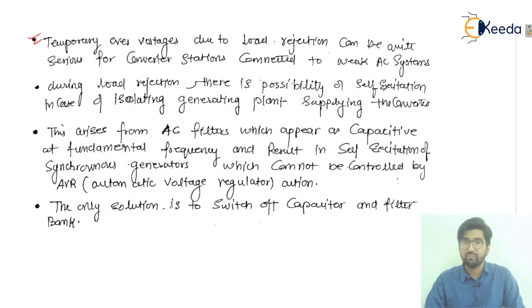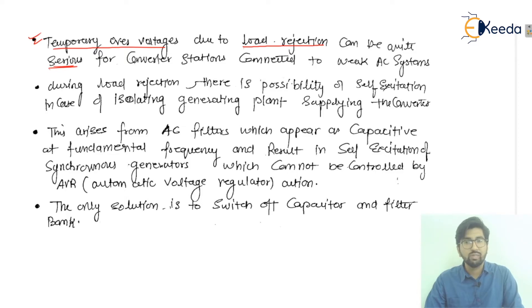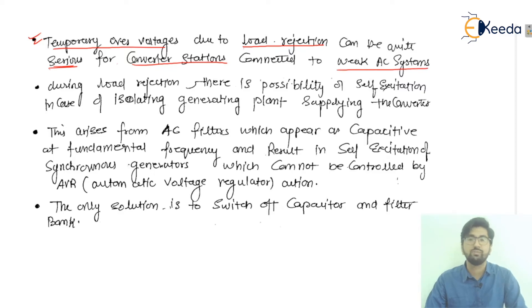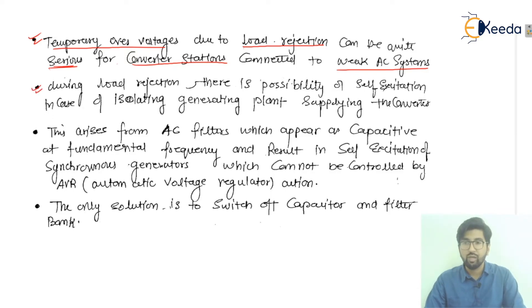Temporary overvoltages due to load rejection can be quite serious. If the load is rejected due to some disturbance, it can be dangerous for the system — especially for converter stations connected to a weak AC system. Whenever we have a weak AC system and the converter station is connected to it, temporary overvoltages can be quite dangerous.